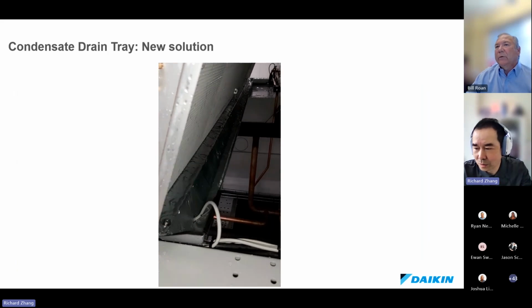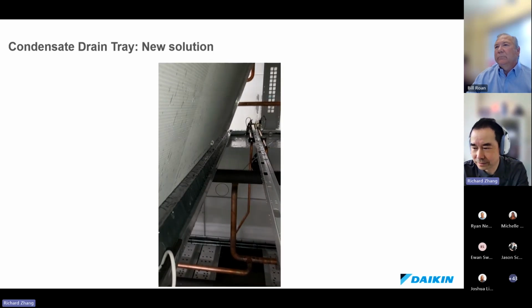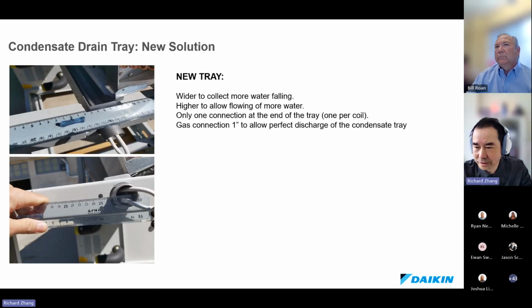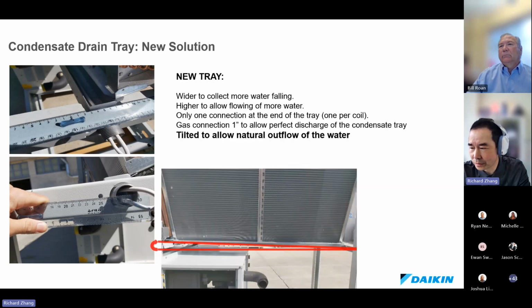The reality is, when you have a huge amount of air going through the coil, you can expect this kind of thing happening when you do the defrost. A lot of water. So we make sure we design the defrost control accessories properly. We have a wider drain pan, on both sides of the coil. We also have an oversized drain pipe. They are also completed with heat trace cable all the way to the roof.